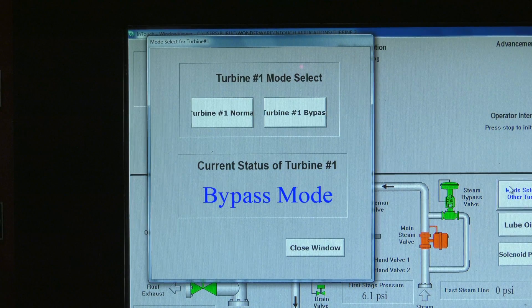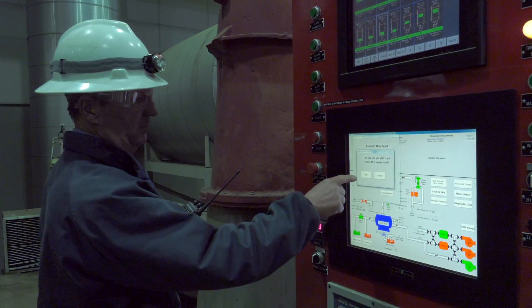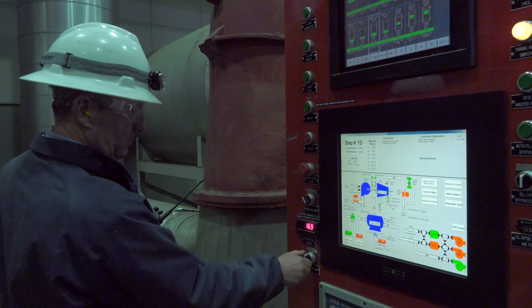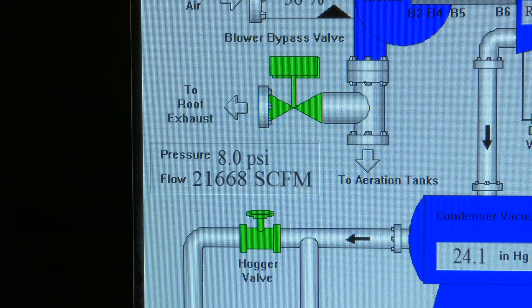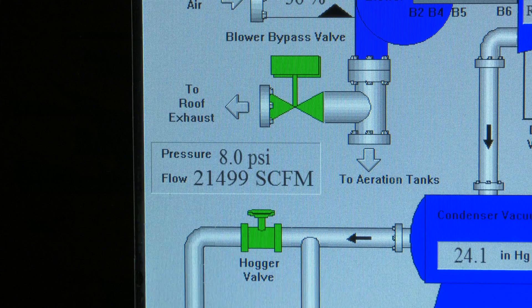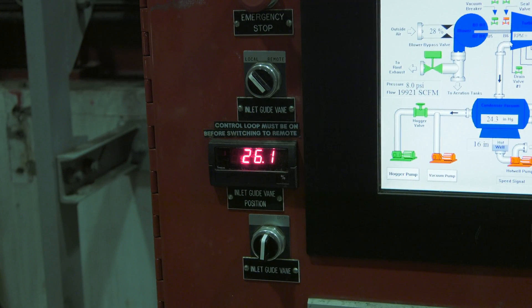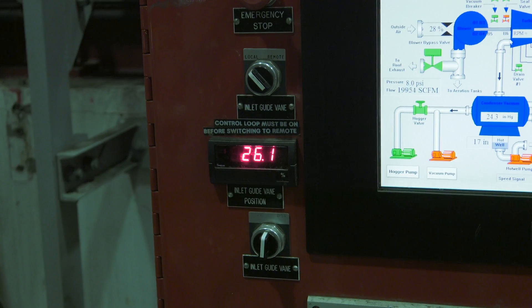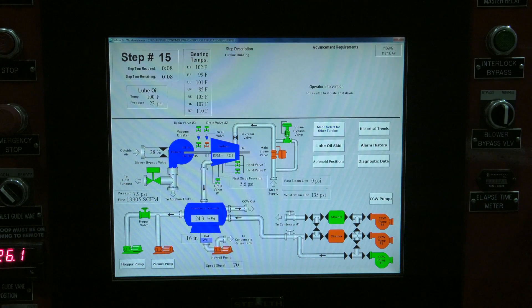If another turbine is online, place the turbine in bypass by pressing the mode select button on the MMI, then press turbine bypass before increasing the guide vanes. If the other turbine is offline, use the open/close toggle to increase the header pressure to 8 PSI on the MMI display. The inlet guide vanes must be more than 25% to satisfy step 13 and advance to step 14. Once the 25% is satisfied, the blower bypass valve will shut and you will be at step 15 online.